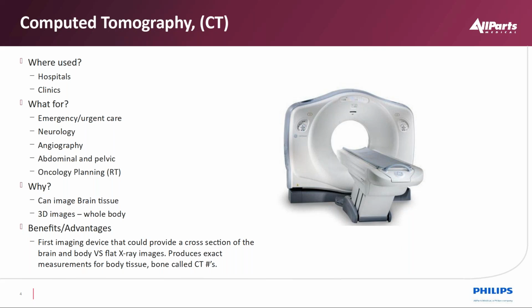So the first imaging device, like we talked about, for brain. But also we do something very exact. We don't just display an image. We display an image based on CT numbers. So those CT numbers represent different materials within your body. Air, blood, water, different body materials have known CT numbers. The scaling system is based on air being one element and then water being the other element. When we talk about water, it's distilled deionized water. That is what we represent on a scale. So on a daily basis, we have to do air cals to update the air every day because of barometric pressure, temperature, a number of air elements within that. So air is updated daily to adjust for any compensation while we scan.